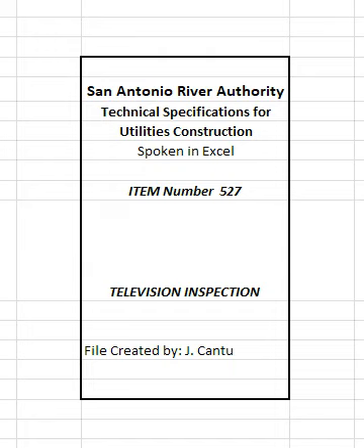527.2. General. This item shall govern for the closed-circuit televising and recording of new line sections selected by the engineer. The interior of the line sections of pipes 8 inches and above shall be carefully inspected after the line has been properly backfilled and successfully air-tested to determine the location and extent of any breaks, obstacles, sags, irregularities in pipe alignment or grade, infiltration or inflow, the location of service connections, or any deficiencies that may degrade the line. The engineer will make the final determination if repairs are required.